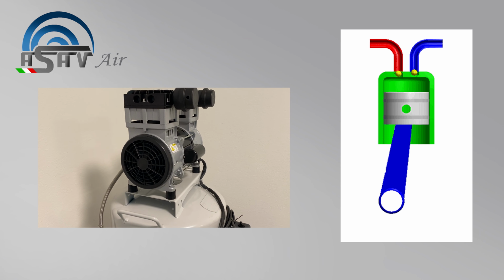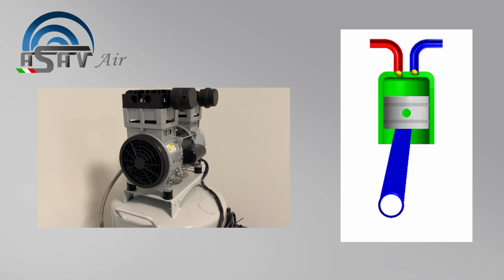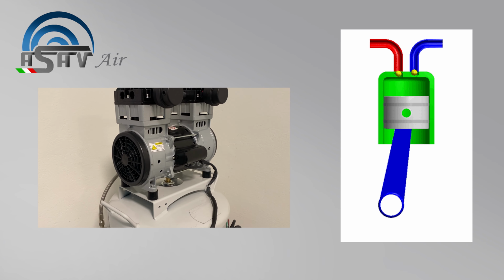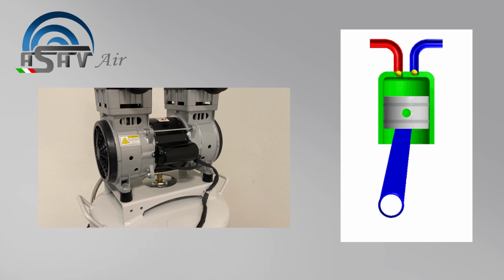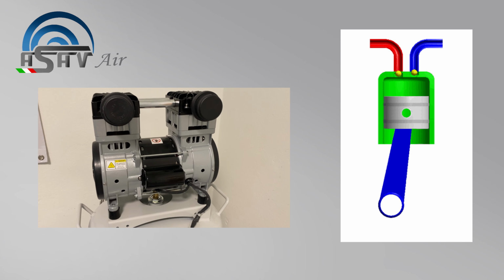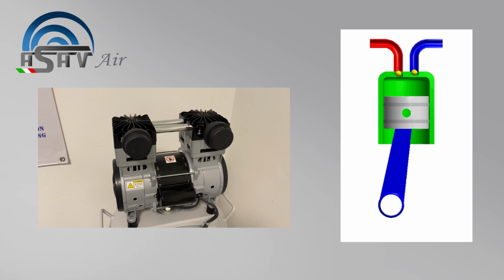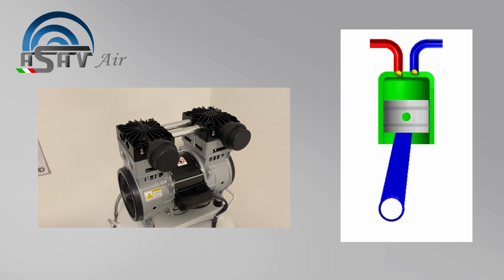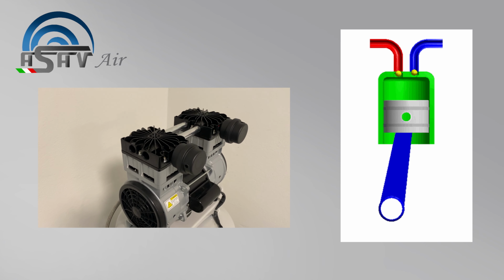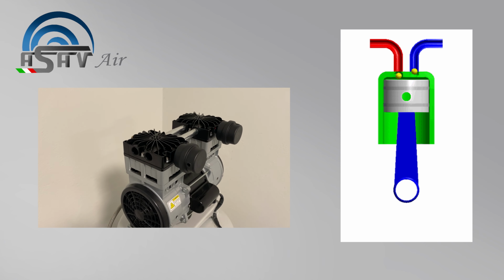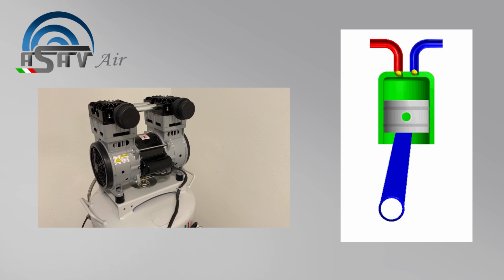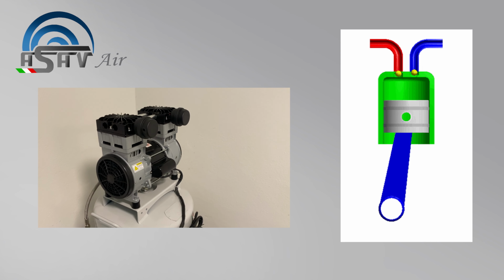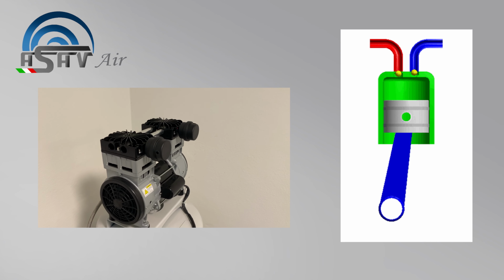The conventional piston compressor has a crankshaft, connecting rod and piston, cylinder and cylinder head. At the top of the cylinder, the head contains the inlet and outlet valves. Both are simply thin membranes, one mounted under the valve plate and the other above it. Moving downwards, the piston creates a vacuum above it, and this allows the outside air at atmospheric pressure to open the inlet valve and fill the area above the piston.